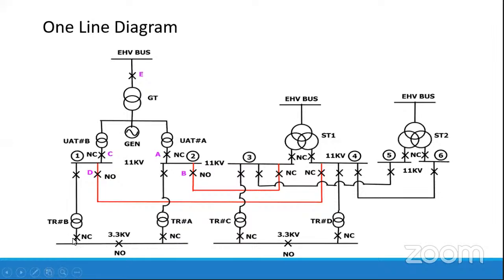So in order to protect, if any kind of fault occurs in this single line diagram, say at the 3.3 bus, then this incomer feeder should isolate first, and only if it fails to operate, then the feeder on the primary side of this transformer should operate. As there are numerous equipments connected in the network, for every equipment certain special protections are taken care of. To protect this transformer, there are protections like differential protection for internal faults and restricted earth fault protection, REF.